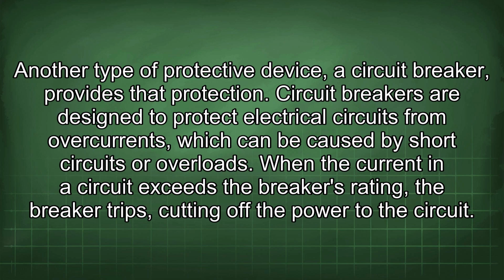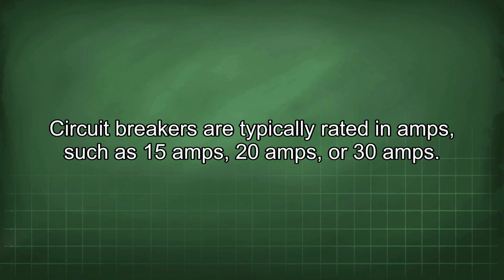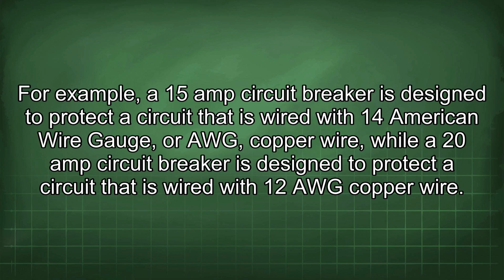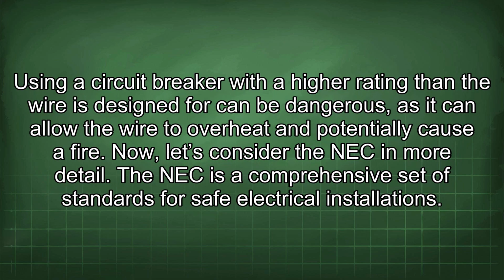Circuit breakers are designed to protect electrical circuits from overcurrents, which can be caused by short circuits or overloads. When the current in a circuit exceeds the breaker's rating, the breaker trips, cutting off the power to the circuit. Circuit breakers are typically rated in amps, such as 15 amps, 20 amps, or 30 amps. For example, a 15-amp circuit breaker is designed to protect a circuit that is wired with 14 American wire gauge, or AWG, copper wire, while a 20-amp circuit breaker is designed to protect a circuit that is wired with 12 AWG copper wire. Using a circuit breaker with a higher rating than the wire is designed for can be dangerous, as it can allow the wire to overheat and potentially cause a fire.